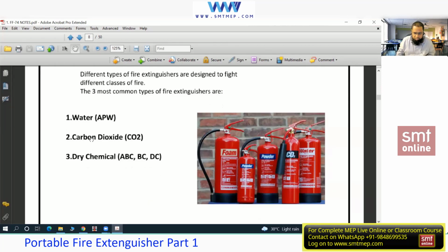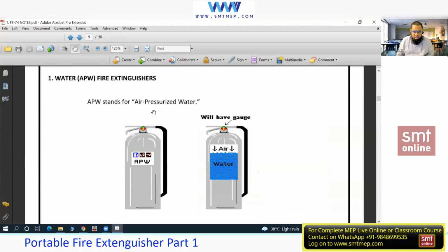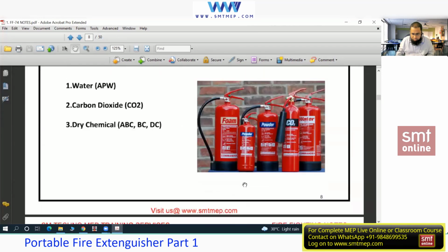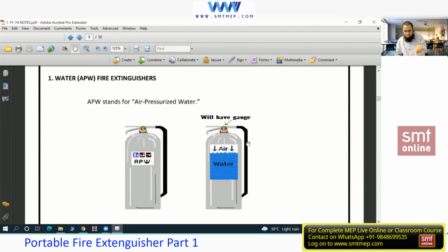Okay, so let me start with water, with some specification. First of all, if you talk about the water type, as I said, we call it APW because it is air pressurized water. It's not like partly air, half water. You'll find the pipe at the bottom, filled with air pressure so that the water can come out when you squeeze the handle, and it is attached to the pipe, not to a horn. In the case of CO2, you'll find a horn-like expander, because CO2 is a gas, and the gas can expand and cover more area when you sweep on the fire. But water is not a gas, so it will not connect with the horn. It will connect with the pipe.